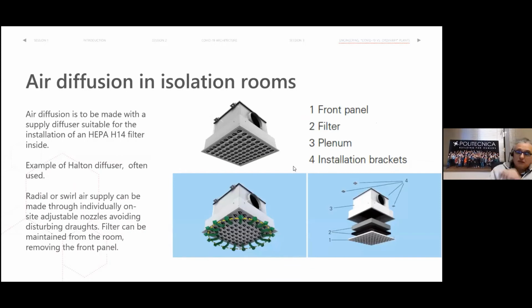The type of diffuser that we generally use is a system like this, which is provided with the H14 HEPA filter inside. You see here, this is the filter which is included in the diffuser. This is a particular diffuser. Halton is the manufacturer, a Finnish company. This is very nice because you can adjust the position of all these nozzles. You can rotate and adjust the position to avoid the downdraft of the air on the patient or whatever. You can adjust the flow all around the room, so this is very flexible. You can have a swirl effect or a radial effect as you like. So it is very flexible, and I suggest to use this kind of diffuser.